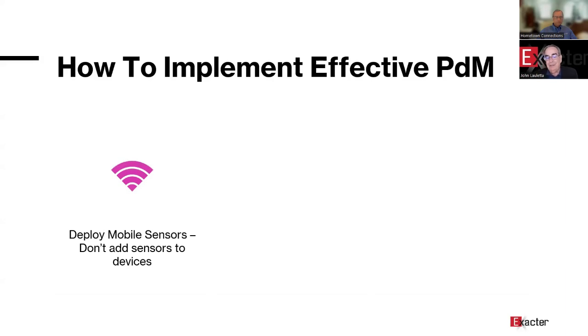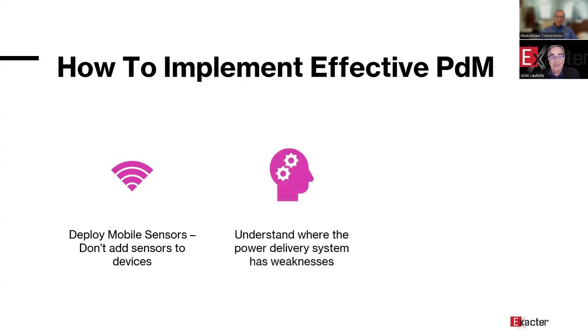So how do you effectively create a predictive maintenance program? Well, we mentioned you have to know the condition of all the equipment on the grid. Now, we could put sensors on all the equipment on the grid, or we could have a sensor that's mobile that visits every pole on a periodic schedule and records and defines the deterioration of the equipment on that pole and gets right down to, on a combination unit, is it the lightning arrestor or is it the cutout itself? Is it the bushing on a transformer or is it the transformer? So getting right down to that rifle shot result can be done, and we'll show you how, using deployed mobile sensors that move from pole to pole and measure the condition of the electrical equipment.